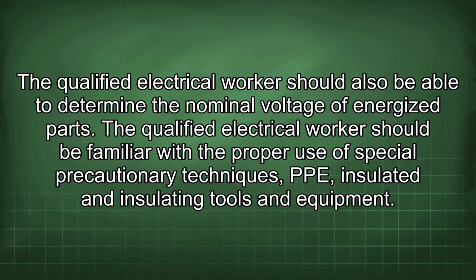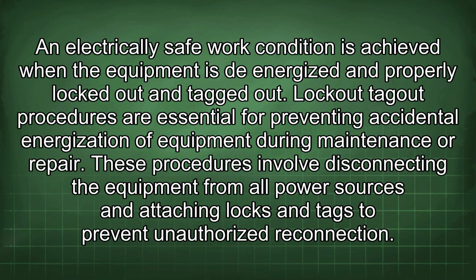An electrically safe work condition is achieved when the equipment is de-energized and properly locked out and tagged out. Lockout-tagout procedures are essential for preventing accidental energization of equipment during maintenance or repair. These procedures involve disconnecting the equipment from all power sources and attaching locks and tags to prevent unauthorized reconnection.